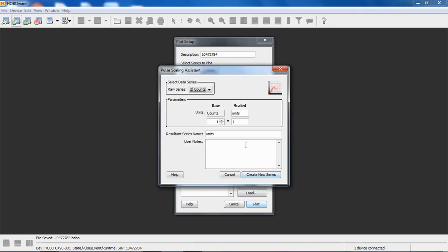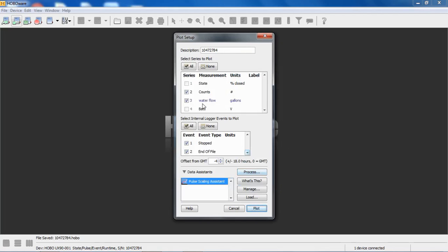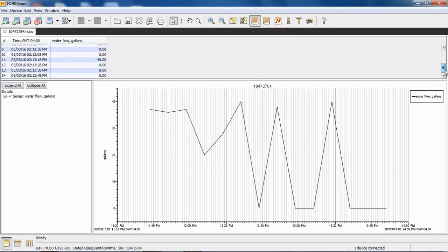I get that same window open, and I can give this a value. Let's use our flow meter: one count equals one gallon, and we're going to say water flow. Now we're basically creating a new series called water flow in gallons. We can include the raw counts or exclude them. I'm going to exclude them from the plot and plot the data. Now we see how many gallons we saw for each interval of data.